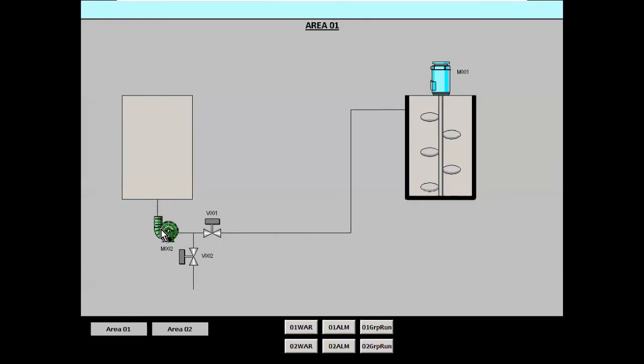How do you know that the actual fluid we have in here, which I said might be sticky, is actually flowing? You might need to have a flow switch. Is it now a high flow switch or a low flow switch? Do you need a flow indicator? Do you need a pressure indicator? Do you need to have some sort of cleaning on the pump? They talk about a gland valve in the mining industry with all the slurry they have.